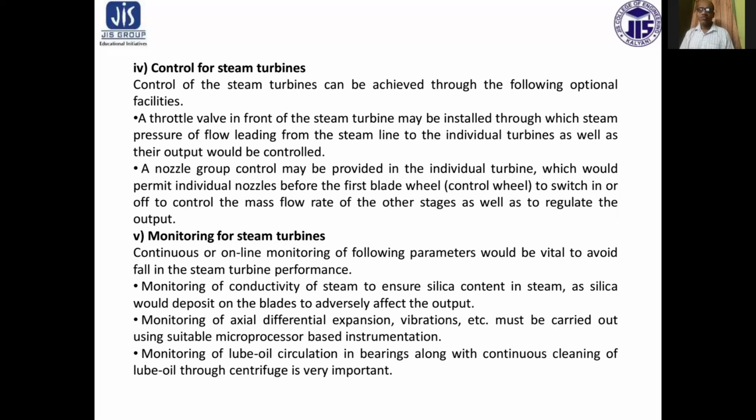Number 5, monitoring of steam turbine. Continuous or online monitoring of following parameters would be vital to avoid fall in the steam turbine performance. Monitoring of conductivity of steam to ensure silica content in steam, as silica would deposit on the blades to adversely affect the output.